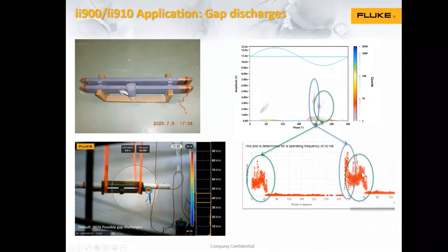Again, it shows the same. Here it has more than one PD source, at least two or three. First it's Corona here, gap discharges here, and maybe something internal, maybe not. I'm not 100% sure.